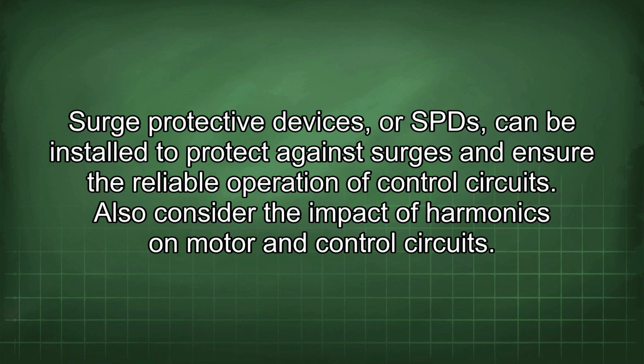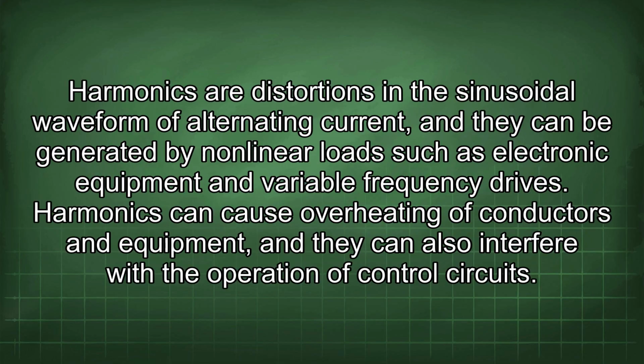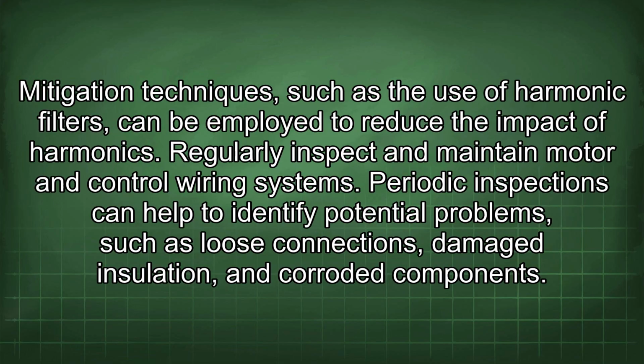Also consider the impact of harmonics on motor and control circuits. Harmonics are distortions in the sinusoidal waveform of alternating current, and they can be generated by nonlinear loads such as electronic equipment and variable frequency drives. Harmonics can cause overheating of conductors and equipment, and they can also interfere with the operation of control circuits. Mitigation techniques, such as the use of harmonic filters, can be employed to reduce the impact of harmonics.